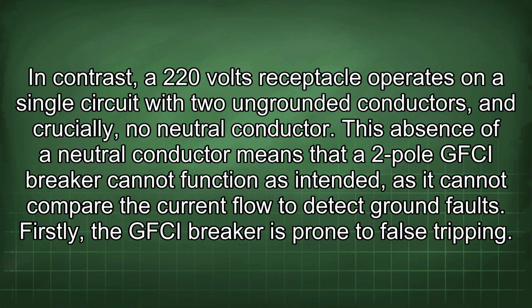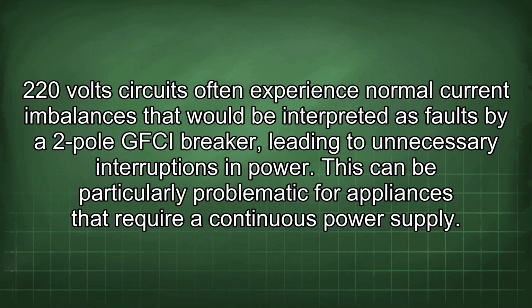Firstly, the GFCI breaker is prone to false tripping. 220 volt circuits often experience normal current imbalances that would be interpreted as faults by a 2-pole GFCI breaker, leading to unnecessary interruptions in power. This can be particularly problematic for appliances that require a continuous power supply.